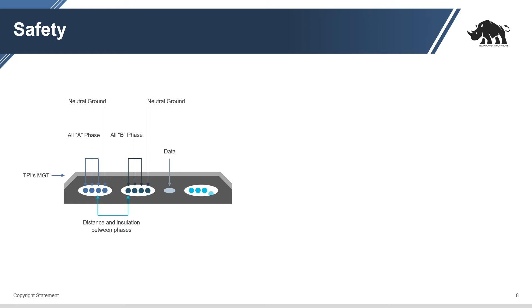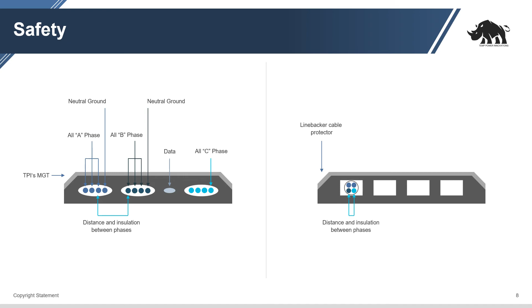Separation of phases inside the cable protector, our MGT, reduces the chance of phase-to-phase short circuit events. Our ungrounded system coupled with high resistance ground detect circuits will alarm on a single phase to ground event before the catastrophic phase-to-phase short circuit and possible arc flash event. These ground detect circuits are simple but have never been incorporated in any Kiewit temp power scheme.